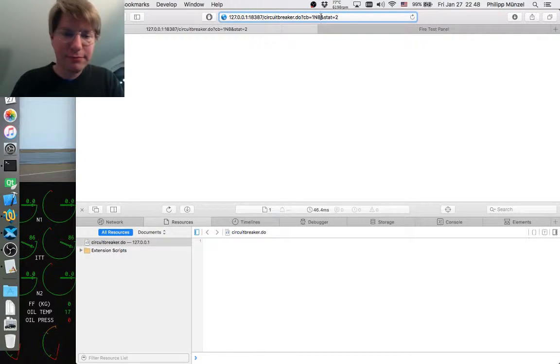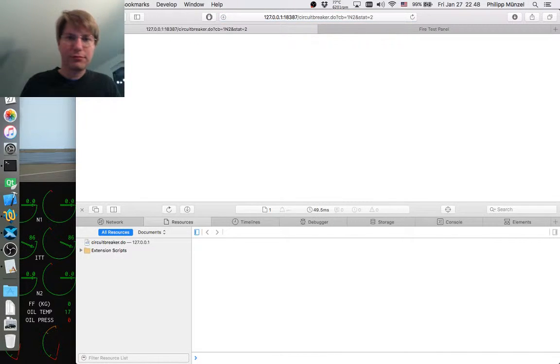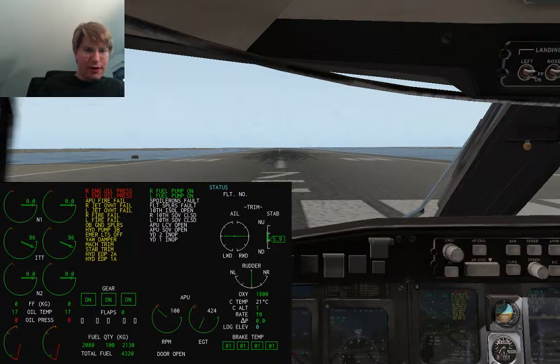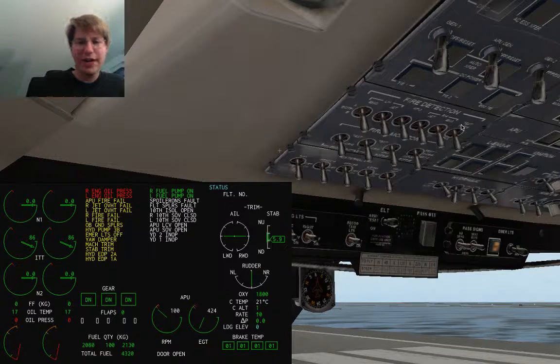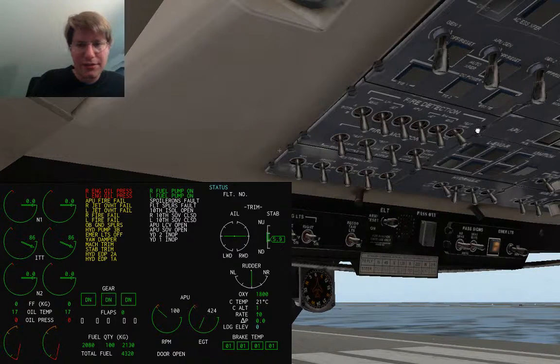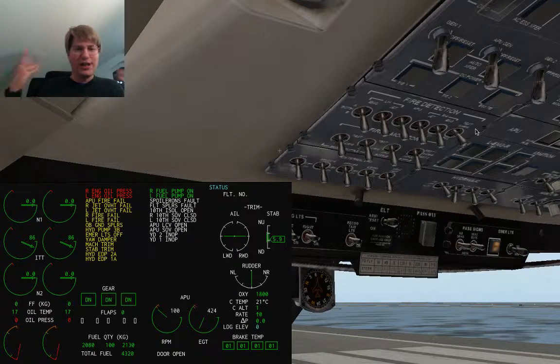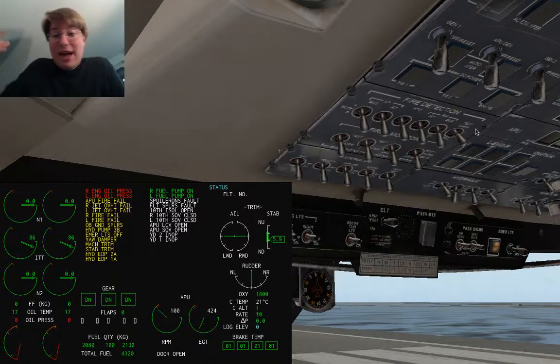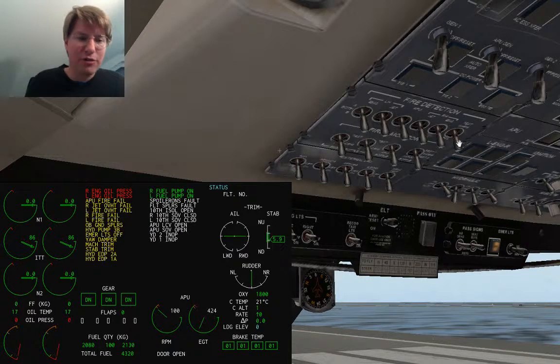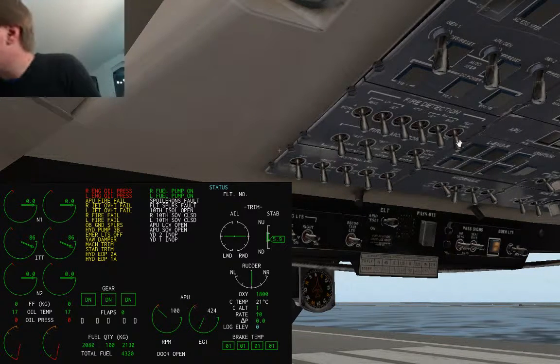Let's kill that, and 2 as well. Bam, it's gone. So now we have APU fire fail, jet pipe overheat fail, fire fail, all that stuff. Now our fire test before starting the engines would produce a different array of warnings. If I turn on the test switch, it engages both loops, and nothing happens — because I've just failed the loops, since I pulled the circuit breakers.